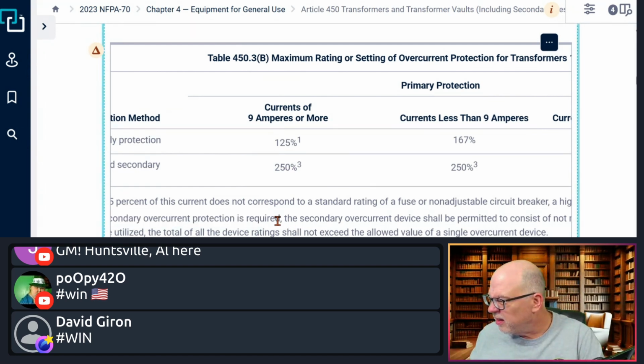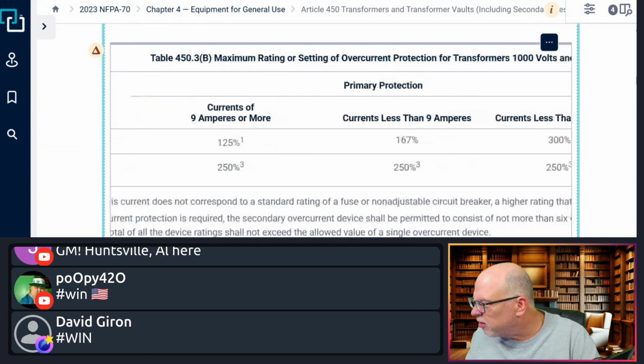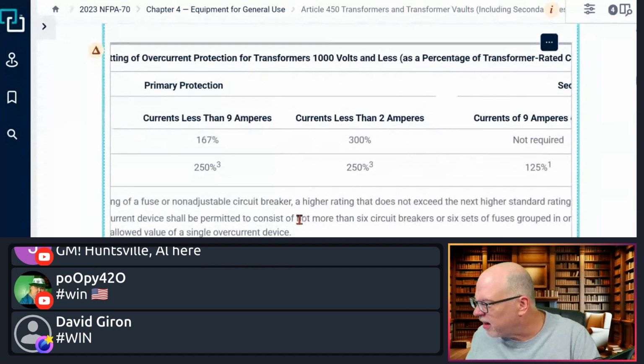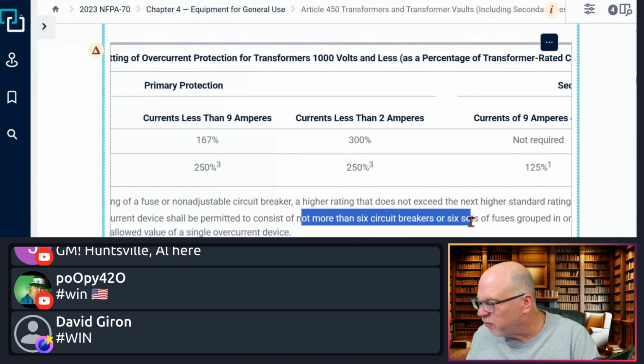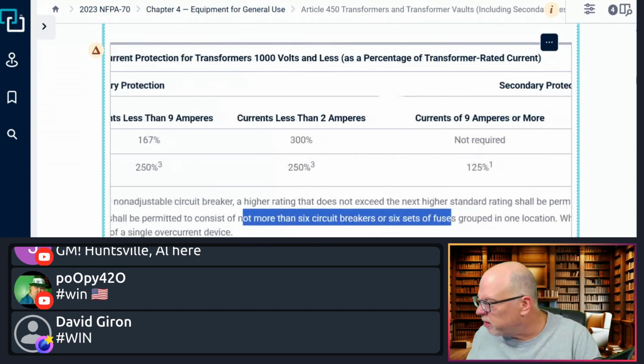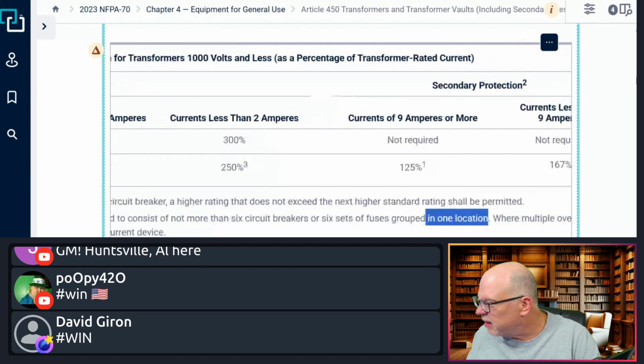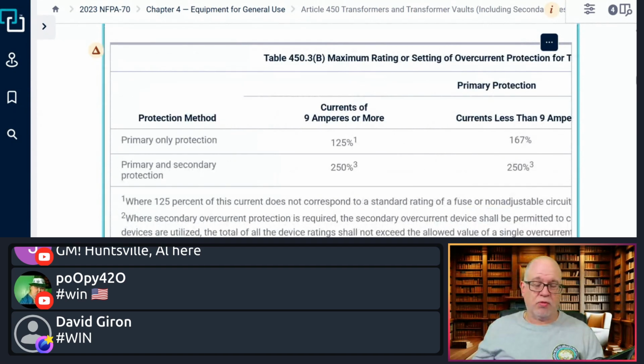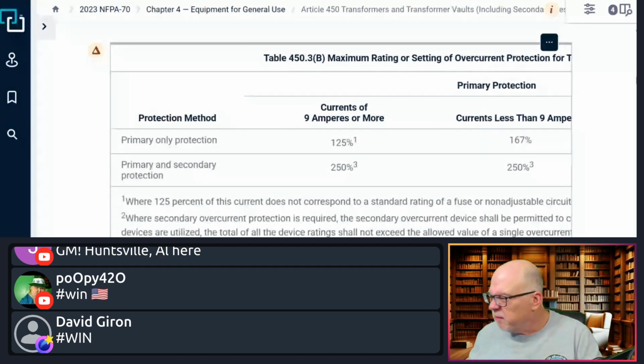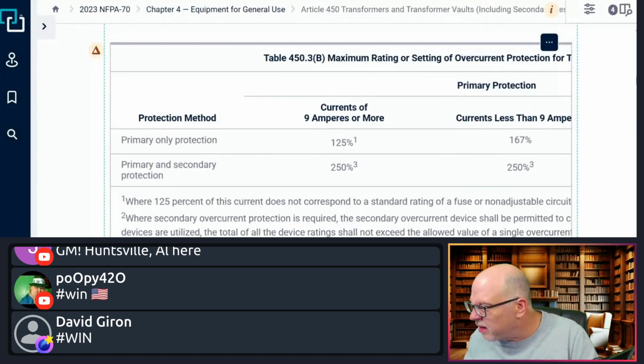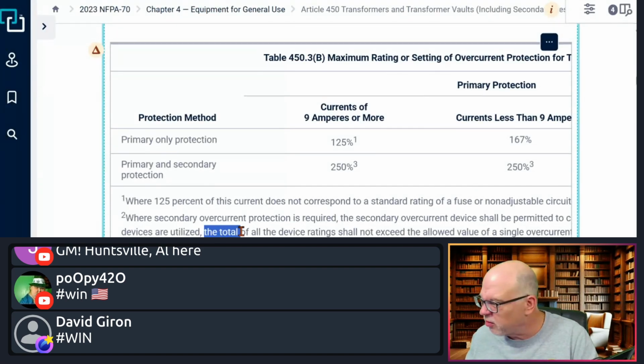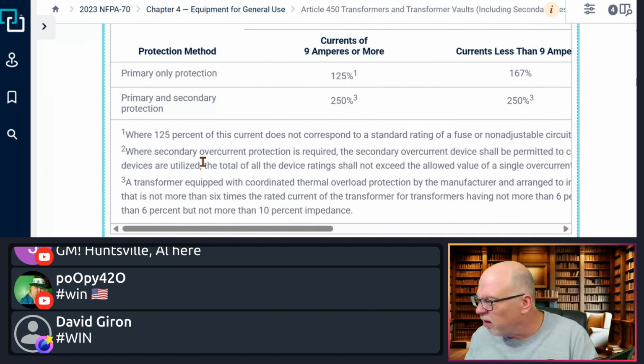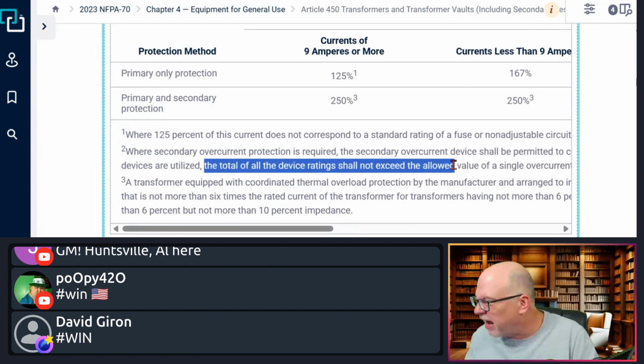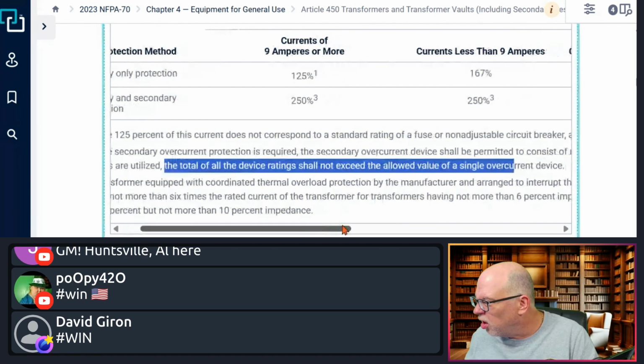It says the secondary overcurrent device shall be permitted to consist of not more than 6 circuit breakers or 6 sets of fuses grouped in one location. Okay. Right, so that's where it gets the rules for that. So we still have the 6 allowed. But what it says at the end of that, I'll scroll down there. It says the total of all device ratings shall not exceed the allowed value of a single overcurrent device.